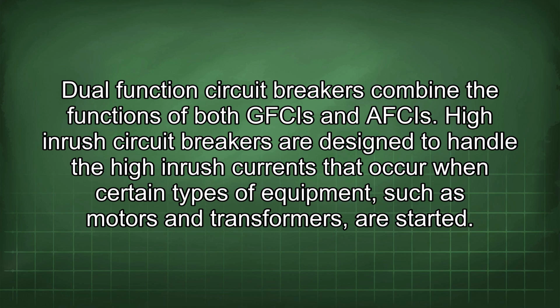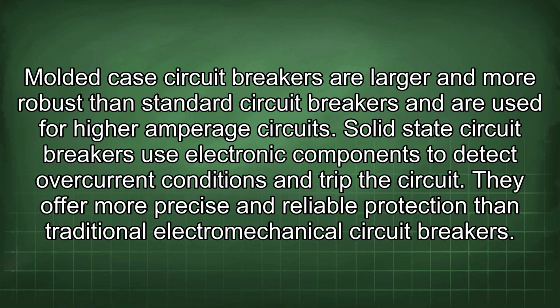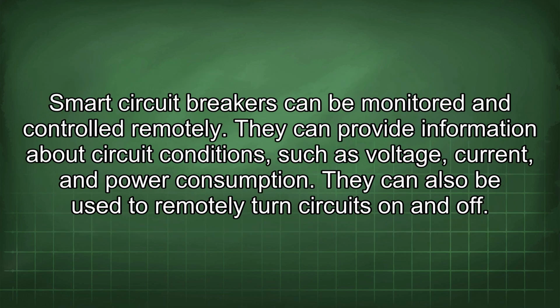High-inrush circuit breakers are designed to handle the high inrush currents that occur when certain types of equipment, such as motors and transformers, are started. Molded case circuit breakers are larger and more robust than standard circuit breakers and are used for higher amperage circuits. Solid-state circuit breakers use electronic components to detect overcurrent conditions and trip the circuit. They offer more precise and reliable protection than traditional electromechanical circuit breakers. Smart circuit breakers can be monitored and controlled remotely. They can provide information about circuit conditions such as voltage, current, and power consumption. They can also be used to remotely turn circuits on and off.